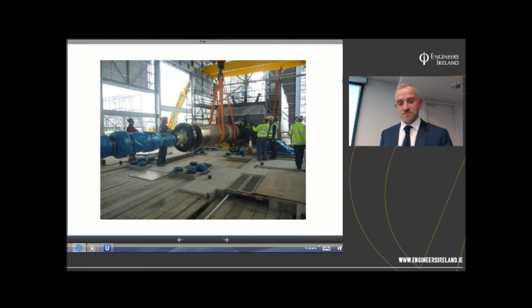And then after the simple cycle, we've got the exhaust hot air from the gas turbine. So the exhaust air from the gas turbine comes out at about 612 degrees Celsius. In a simple cycle situation, that just gets released into the atmosphere and is lost. So in our combined cycle, we take that 612 degrees and use that energy to convert water into steam to drive a steam turbine in the system as well.